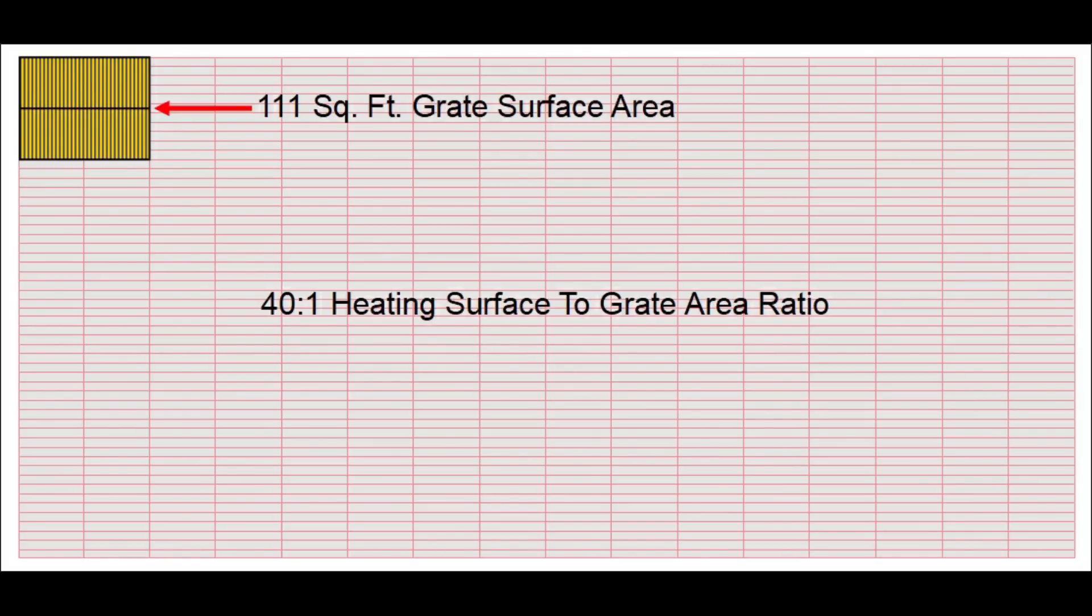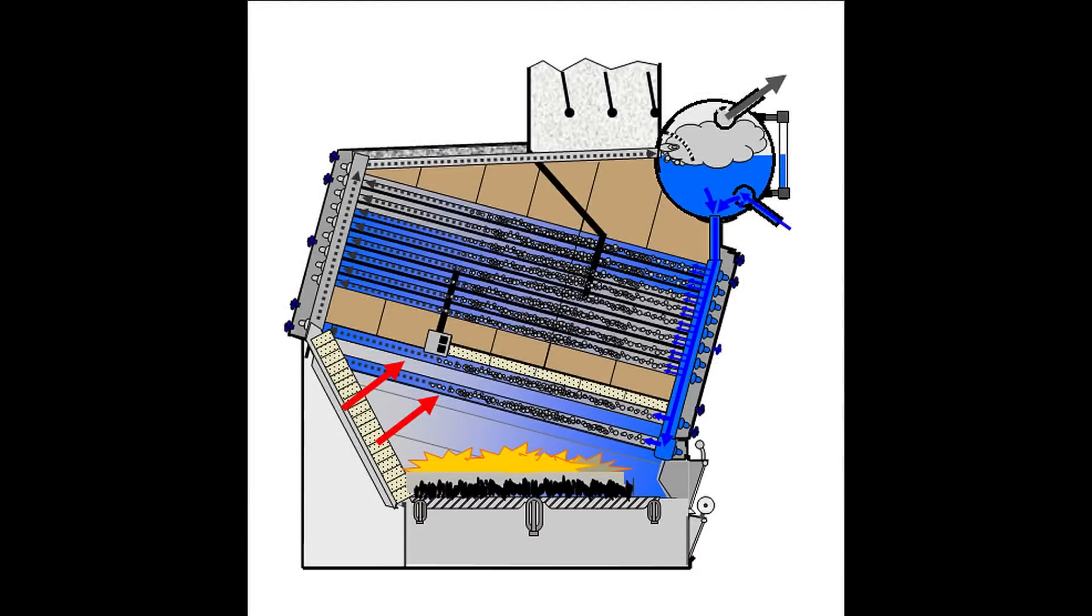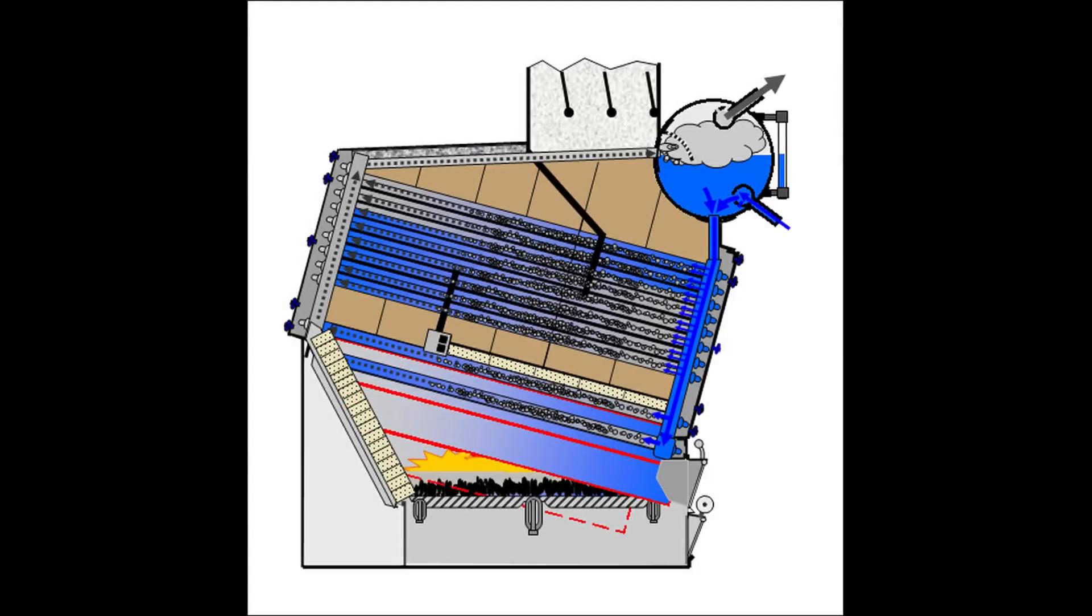It should be clear that the two variables were very closely related since fire grate size determined fire size and heat production and tube surface area determined how much heat would pass to the water and generate steam. This relationship can be expressed as a ratio, which in this case was 40 to 1 tube-generating surface to fire grate size. That was a very good number. A smaller ratio would allow fast steaming response, but a lot of heat would pass through and out the smokestack. Conversely, a larger ratio would result in more water than available heat needed to create the steam. Even that large number of tubes didn't get the most out of the heat of burning coal. If you take a closer look at the firebox, you'll see two additional rows of tubes suspended below its sloped roof that took heat directly off the fire. Water jackets also ran along both sides of the firebox that served double duty. They not only added to the generation of steam, they also acted as barriers that substantially reduced the heat conducted through to the boiler side walls and escaped into the room.